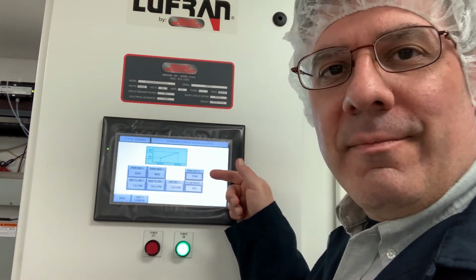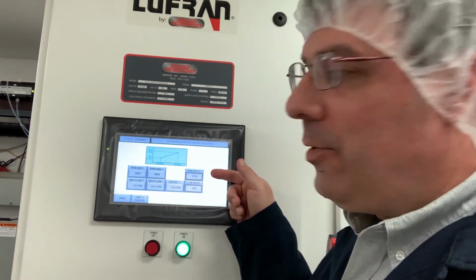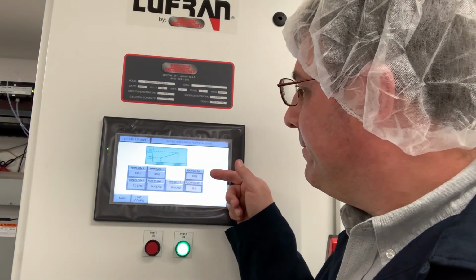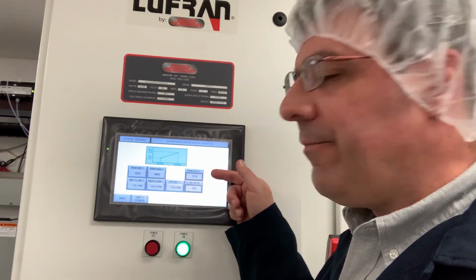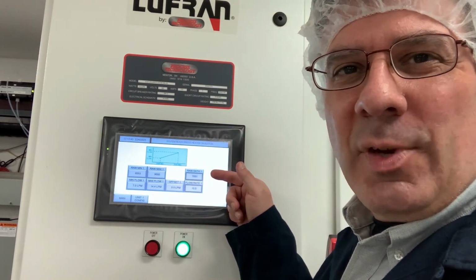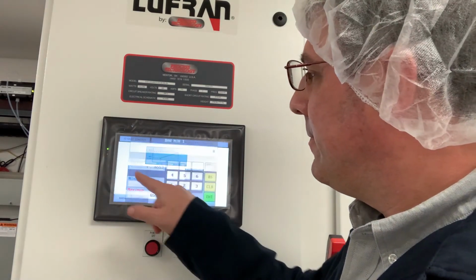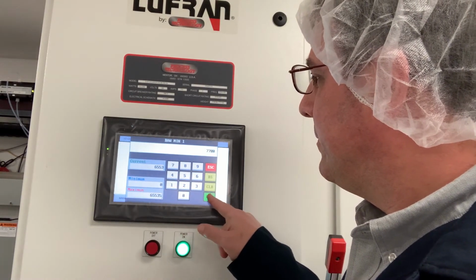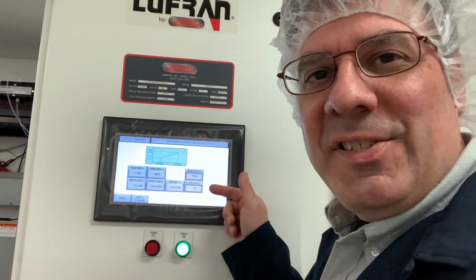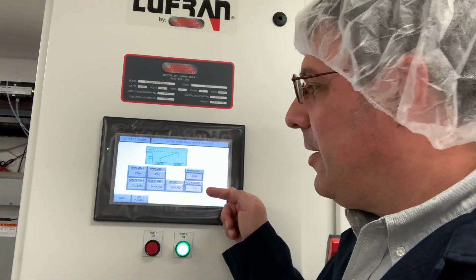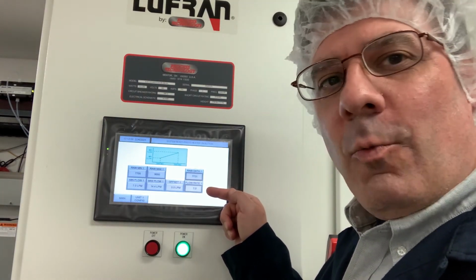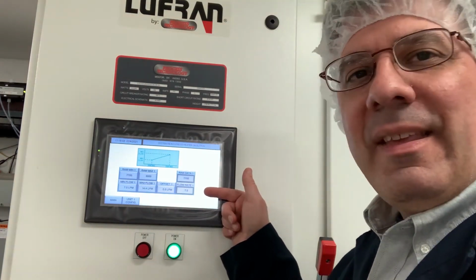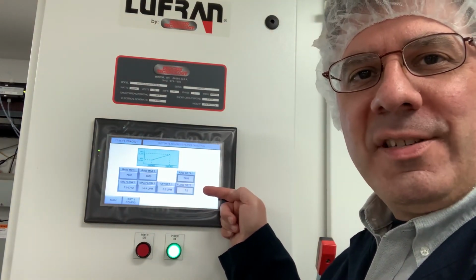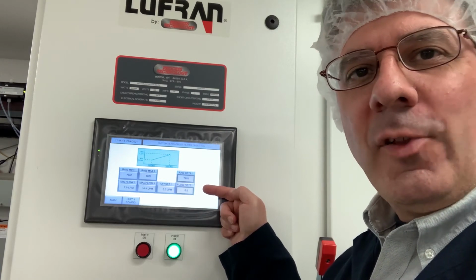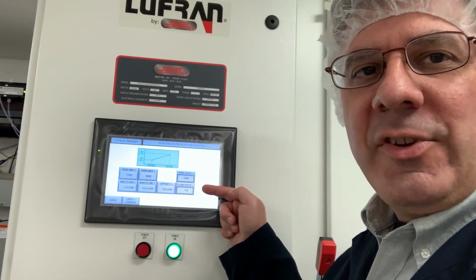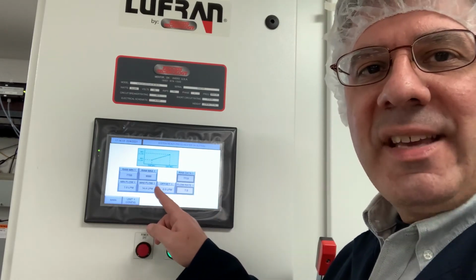Now we're going to take a look at the raw data number and enter that value for the raw min. It's right around 7,700, so that's what I'm going to enter for starters. The next step is to check, does this value here, your flow rate, agree with the flow meter on the back? As you can see, our flow meter indicator right here is at 7 liters a minute. That agrees with the flow meter value on the other side. So we've adjusted the minimum flow and the maximum flow.